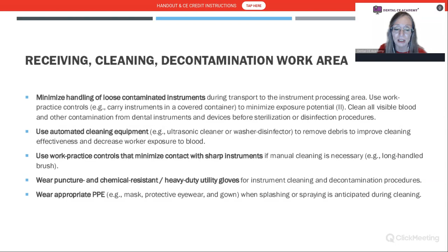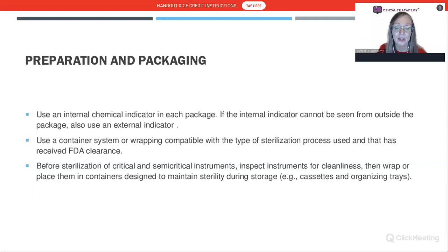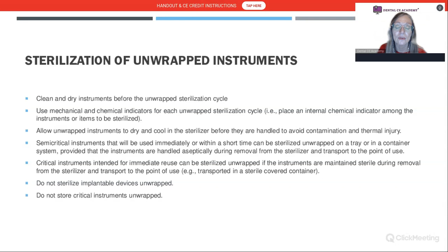For preparation and packaging, we're going to use an internal chemical indicator, use a container system or a wrapping system that's compatible with the type of sterilization process you use that has FDA clearance. Always inspect your instruments for cleanliness before you wrap them and autoclave them. Unwrapped instruments. We don't sterilize implantable devices unwrapped, and we don't store critical instruments unwrapped, and we have to handle them in a sterile fashion. Storage area for sterilized items and clean dental supplies. As said, we are going to store these separate from contaminated.